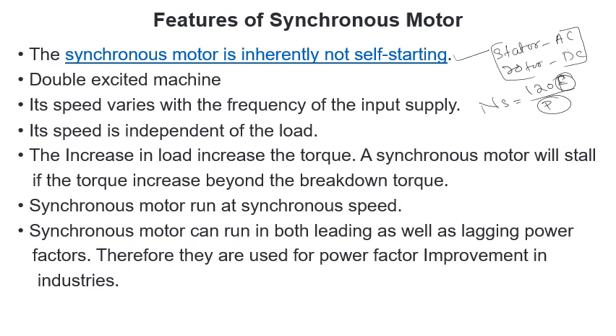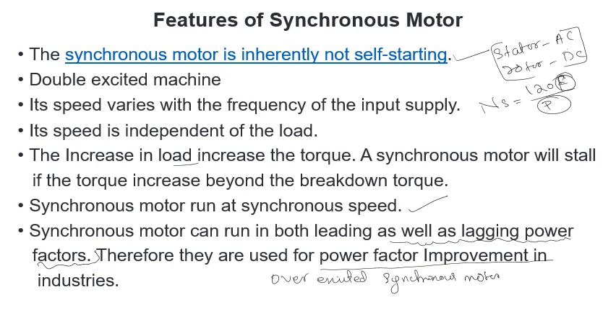Speed is independent of load — if we increase the load, the torque also increases but it runs at synchronous speed. Another important point is that synchronous motors can run at both lagging and leading power factors, so they can be used for power factor improvement. Over-excited synchronous motors are known as synchronous condensers, and these synchronous condensers can be used to improve power factors in industries and in transmission systems. These are the main features of a synchronous motor and are very important from an exam point of view.